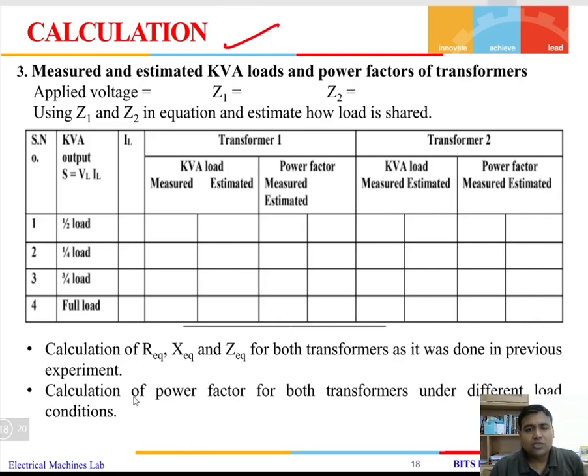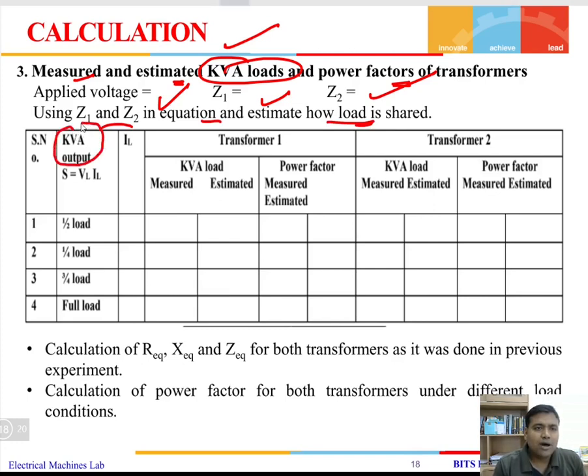So what is the calculation that we need to do? The measured and estimated kVA load and power factor of the transformers we need to find. The applied voltage we have to note down, and Z1 and Z2 are the impedances of transformer 1 and 2. Then using Z1 and Z2 in the equation, we have to obtain how the load is shared. The kVA output, that is the complex power output, is the product of the load voltage and the load current, and we are going to take different load conditions: quarter load, half load, 3/4 load, and the full load condition.